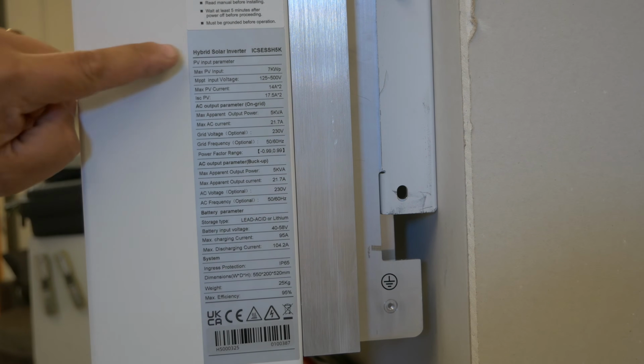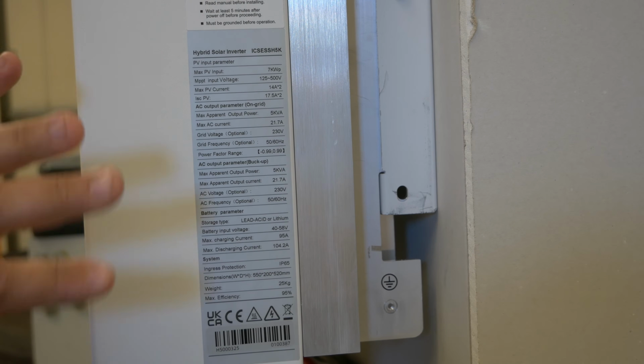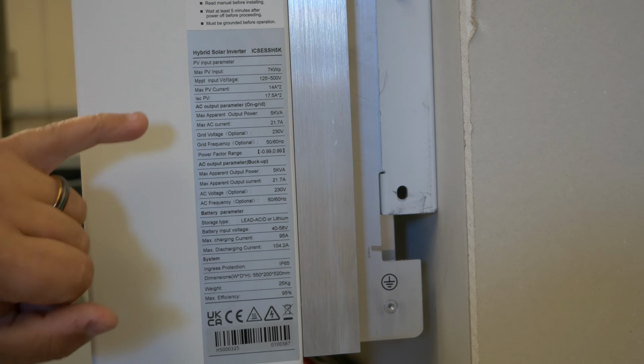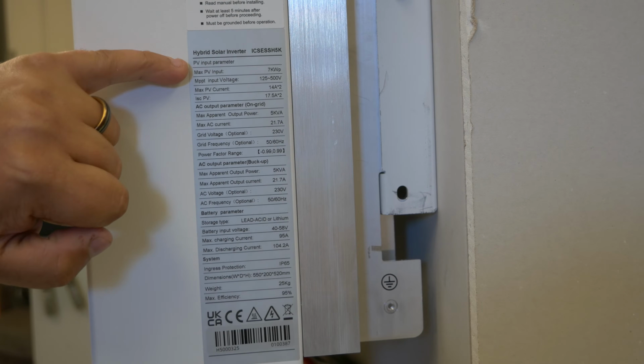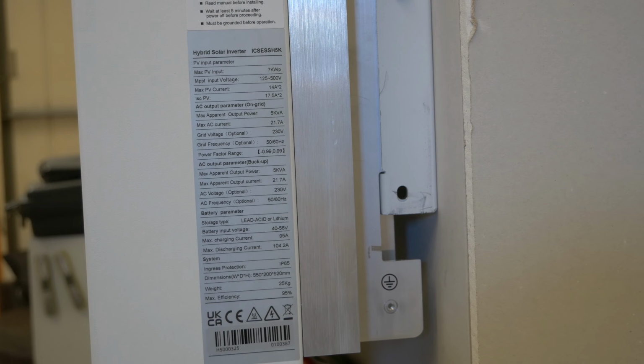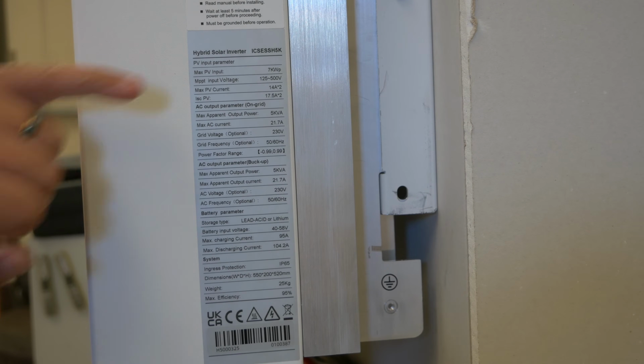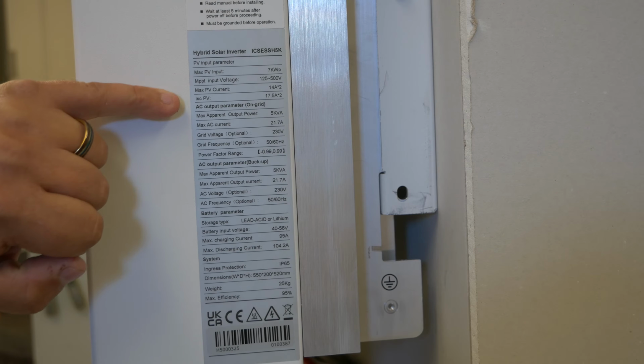We can see on the side of the inverter it comes with a list of all the outputs this thing can do. This is the 5 kilowatt inverter, but it has a PV peak of 7 kilowatts. Its input voltage range for the MPPTs is 125 to 500 volts, which is why here at Apprentice 121 it's going to be tricky to get this to start using the solar generation, because we've only got about 80 volts or so coming off that and we're indoors, so it's never really going to manifest into a usable voltage and current. But this will do up to 14 amps for the PV current and an ISC of 17.5.